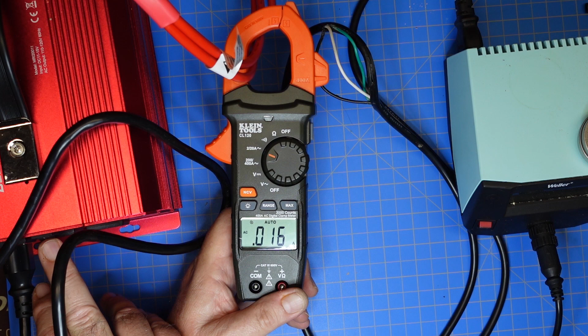There's nothing hooked into the inverter right now. It is on, and it's pulling a few amps, 0.15, and if I turn it off, that'll probably go down to almost nothing. Now it's running the electronics, not doing anything. There we go, there was the inrush as I powered it on and the fans kicked on.